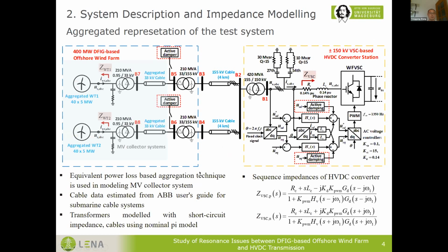So here is the test grid, which is a 400 megawatt DFIG-based offshore wind farm with a 2-level VSC-based HVDC connection. The wind farm medium voltage collector systems are aggregated to two wind turbines from 80 wind turbines, and the wind farm is connected to the HVDC converter station through two short high voltage AC branches. The overall offshore grid can be considered isolated from the main onshore grid, provided that constant DC voltage is maintained for the HVDC connection.